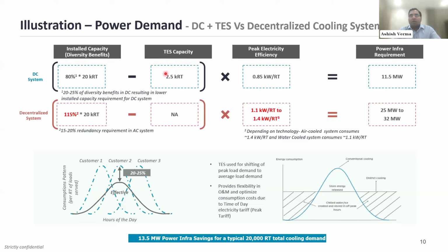When we consider a peak electrical efficiency of a district cooling plant of around 0.85, it can be better than that also, but I have considered a conservative number of 0.85, we'll need a power demand of 11.5 megawatt. Now, compare this with a decentralized system. Mostly, decentralized systems go for additional redundant equipment, which is a necessity because in case of failure of any component they will need standby equipment, and they also don't have the capacity to install TES. So there is around 15 to 20% redundancy in the system design for decentralized systems.